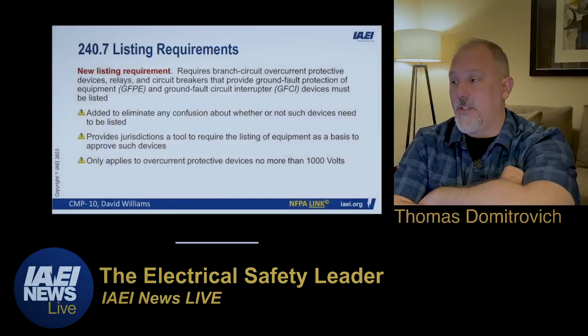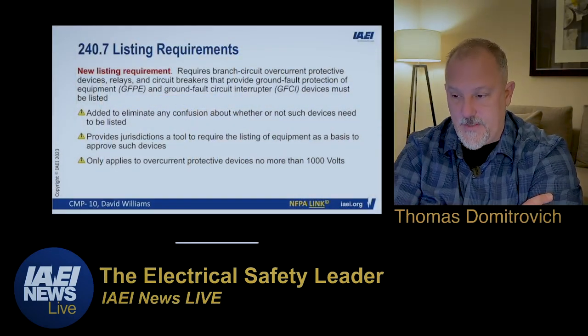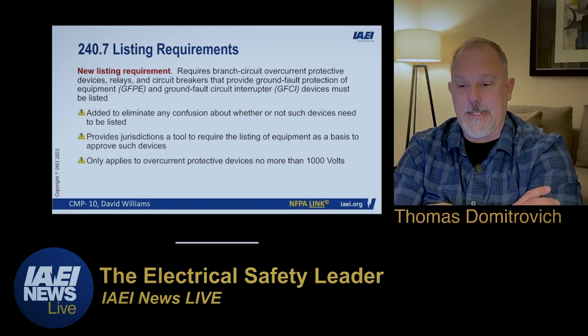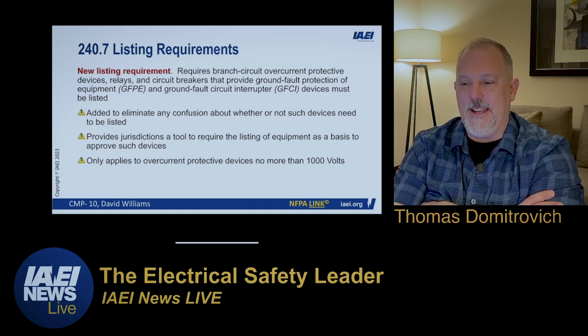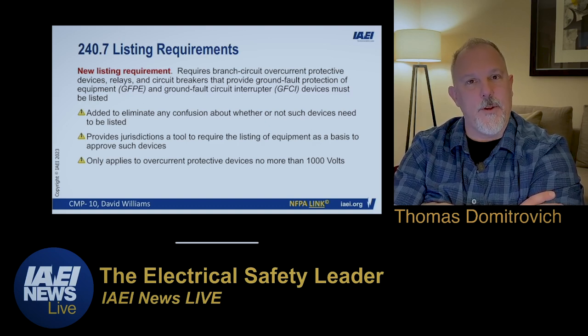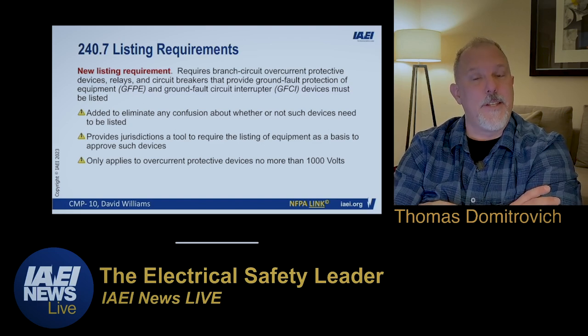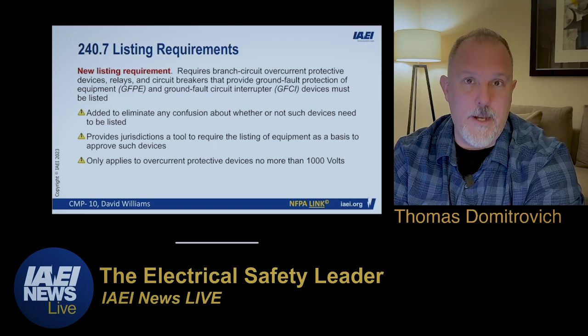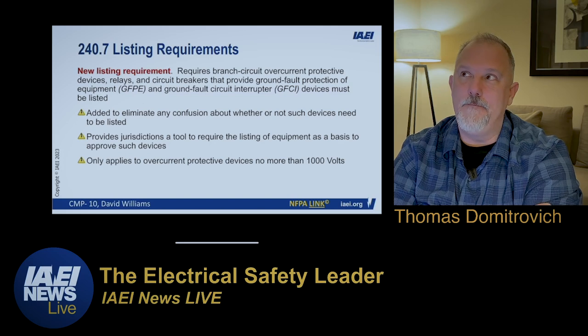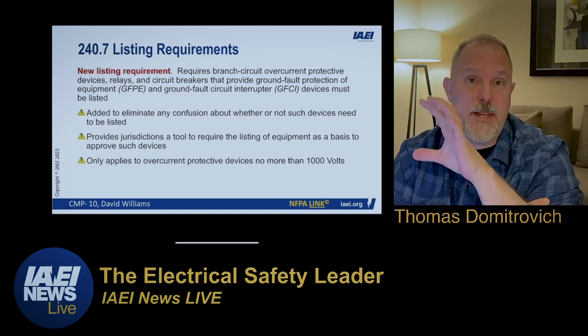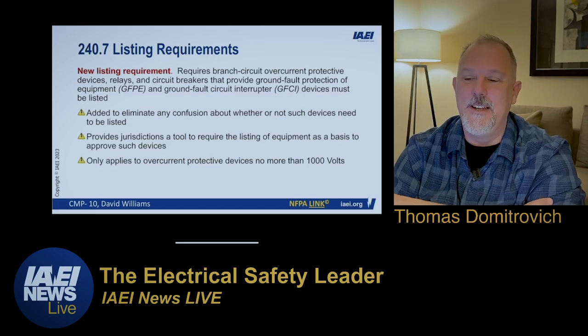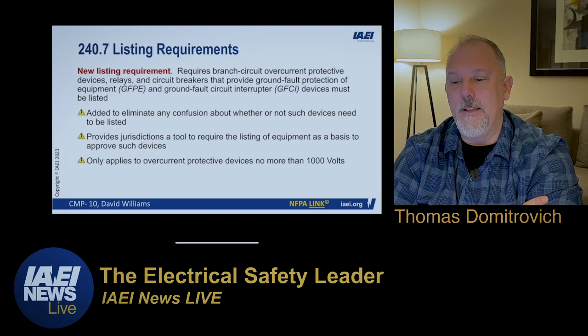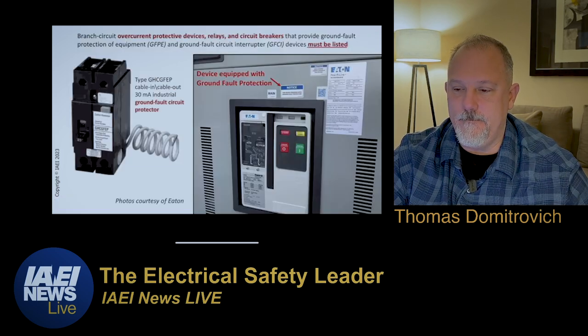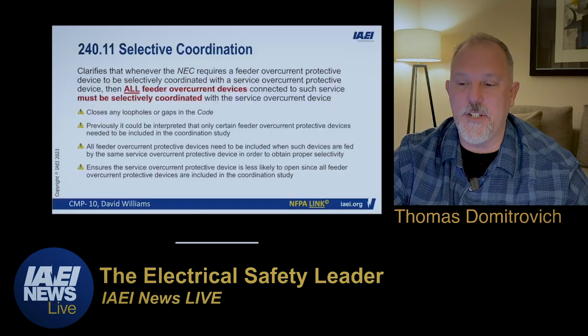All right. And I think, if I'm not mistaken, I'm looking at the presentation, 240.7. Oh, 240.7, listing requirements. Circuit breakers are now required to be listed. GFCIs and ground fault protection of equipment are required to be listed. I was surprised that a branch circuit overcurrent protective device was not required to be listed in the past. Well, it is now. So 240.7, and then you probably have already been looking for the UL mark or the Intertek mark, whatever the mark is from the nationally recognized testing laboratory that provides those marks. But they are required to be listed. And GFPE is required to be listed, so is GFCIs.